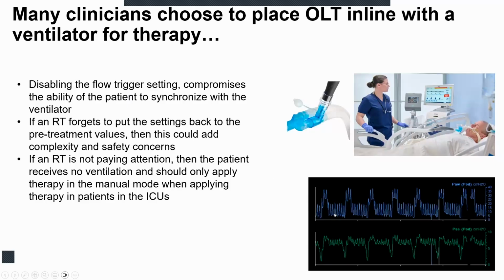A lot of that has to do with the fact that the ventilator is designed to vent any excessive pressure beyond the PEEP level and the pressure control level using a pressure control learn algorithm. That significantly attenuates your oscillations in the circuit and in the lung. When we look at how these are transmitted down through the lung, very little of that pressure is transmitted. Even though you set it at 30 and maybe you're getting 10 for PIP here, very little of that is being transmitted down into the lungs.